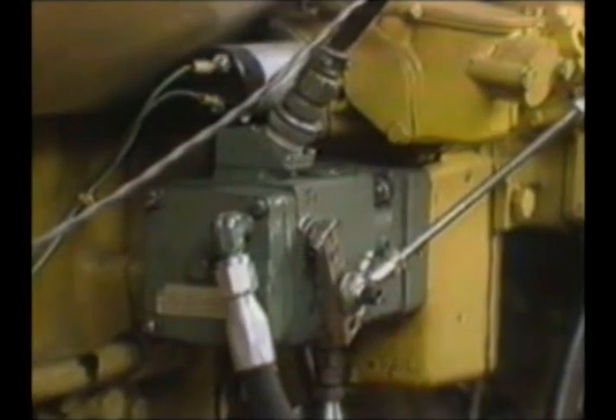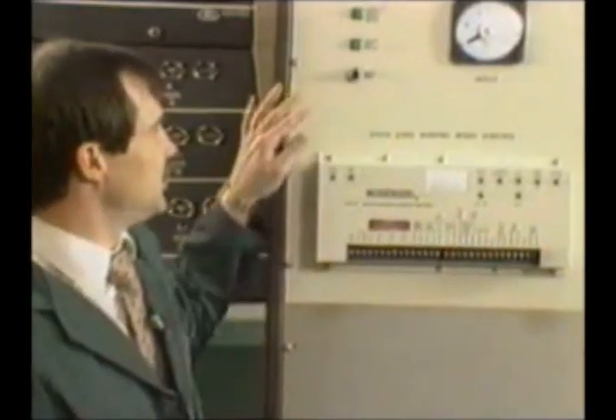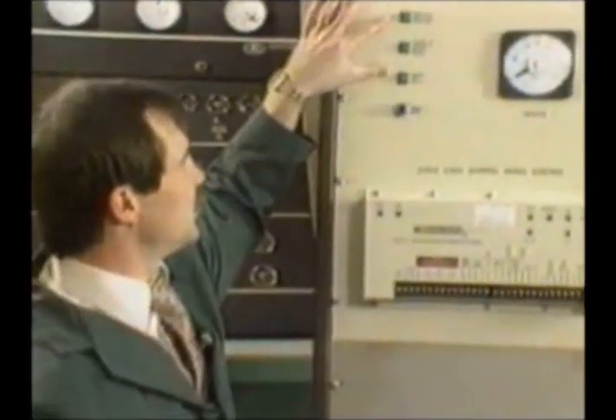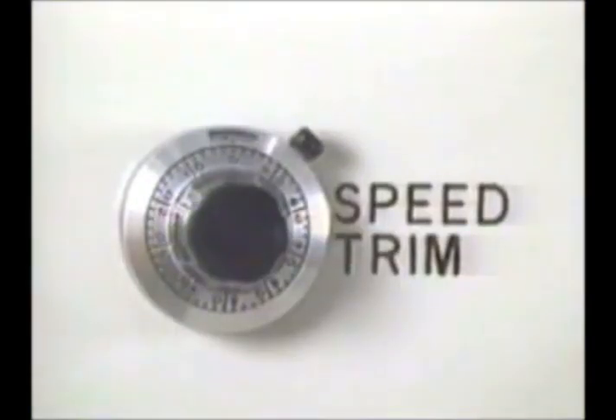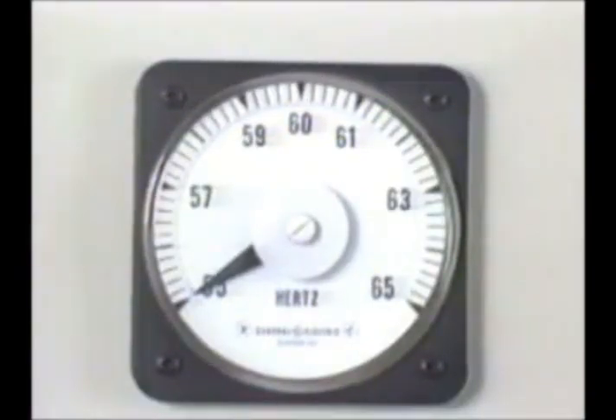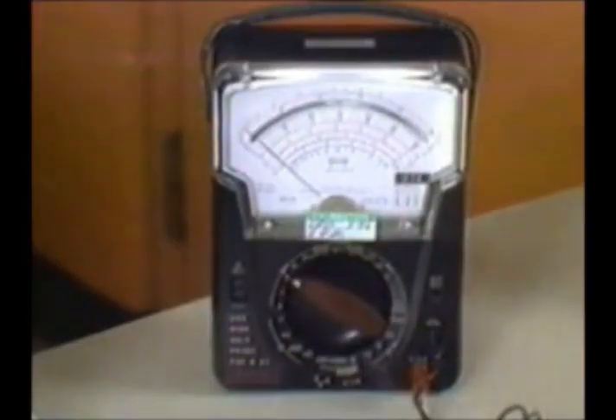Other equipment we'll be using to help demonstrate the 2301A today: on the engine we have an EG3P actuator. We simulate your switch gear with 3 switches. We have a circuit breaker auxiliary contact, close to override failed speed signal, close for rated. We have a speed trim potentiometer. We have a Hertz meter which will vary from 55 to 65 Hertz. We use an analog meter.